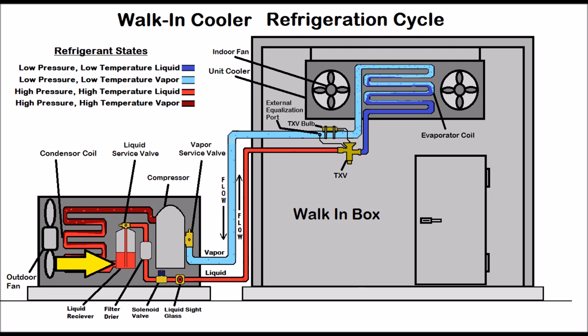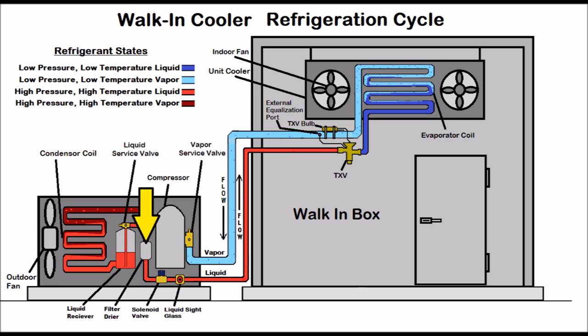The sub-cooled liquid then gets sucked up through the liquid service valve on the top of the receiver and goes through the filter dryer. The filter dryer's job is to store any water vapor and contaminants so that they do not interact with the refrigerant oil. If water vapor and refrigerant oil mix, it turns into alcohol and acids. The sub-cooled liquid refrigerant then heads through the filter dryer and through the solenoid valve.